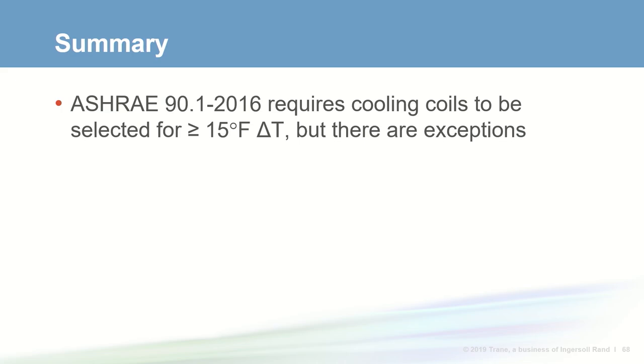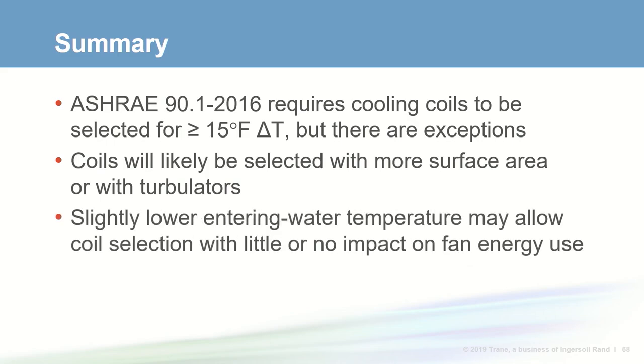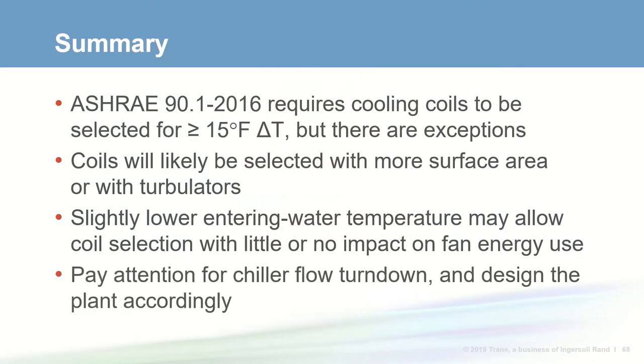In summary: ASHRAE 90.1 now requires cooling coils to be selected for a minimum 15 degree delta T, with some exceptions. The larger delta T reduces water flow rate, allowing smaller valves, pipes, and pumps, and reduces pump energy use. This will likely lead designers to select coils with more surface area or with turbulators. Turbulators allow coils to maintain or even increase delta T at part load, leading to pump energy savings. Designing with a slightly lower chilled water temperature may allow coils to be selected with little or no impact on fan energy use. And when selecting chillers for higher delta Ts, pay close attention to flow turndown — if turndown is poor, consider the impact on your pumping system and design accordingly.